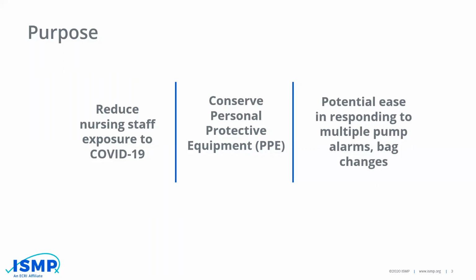And then the other issue was, even nurses walking by in the hallway, it was much easier than going into the patient's room to respond to pump alarms. And as I said, the bag changes. So those were the major reasons for doing this, keeping pumps outside in the hallway.